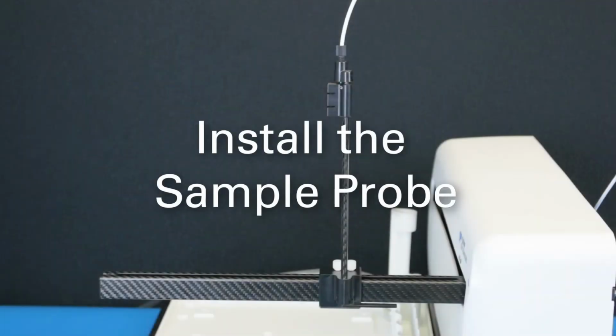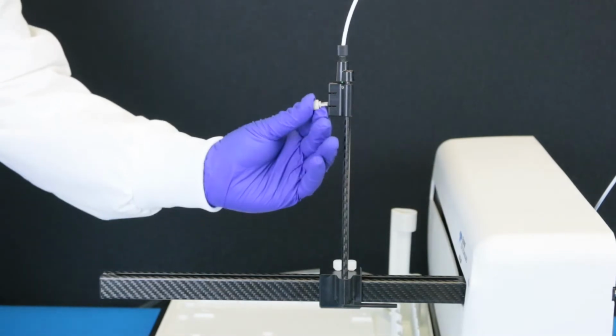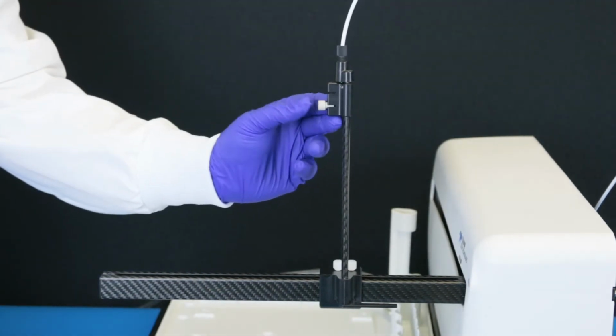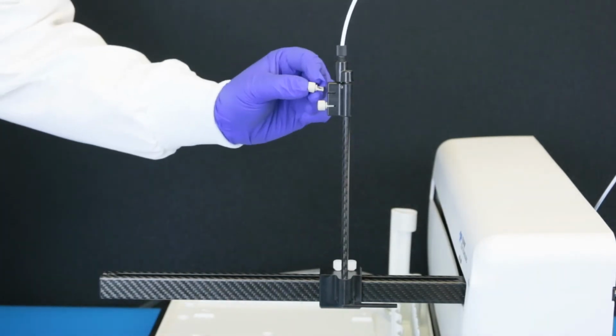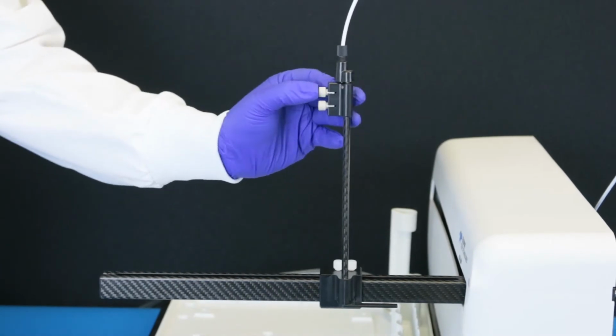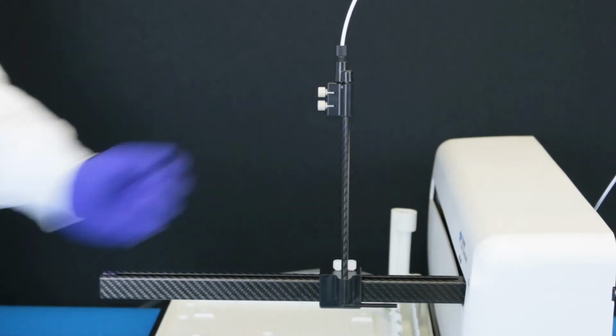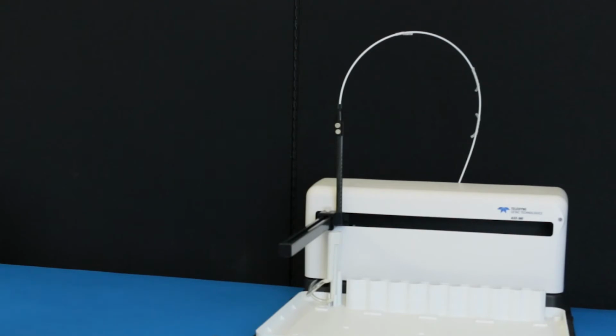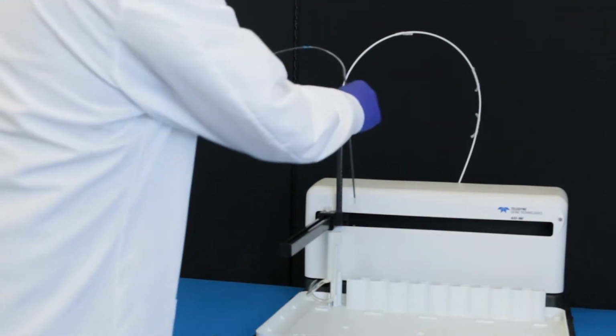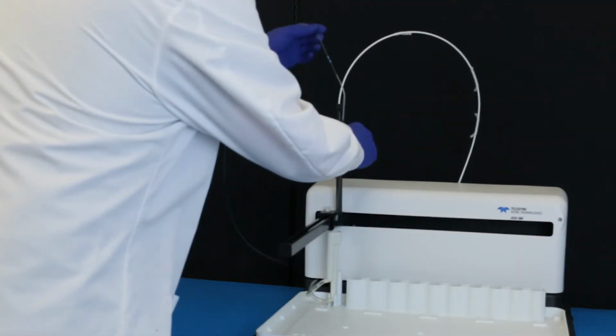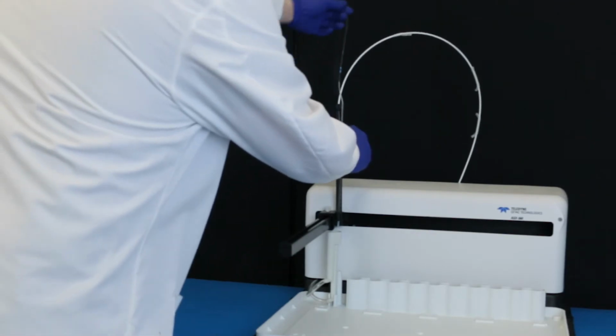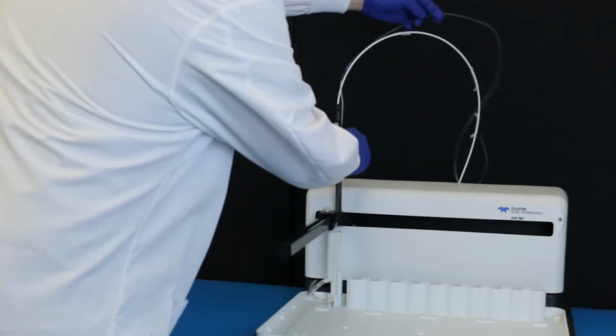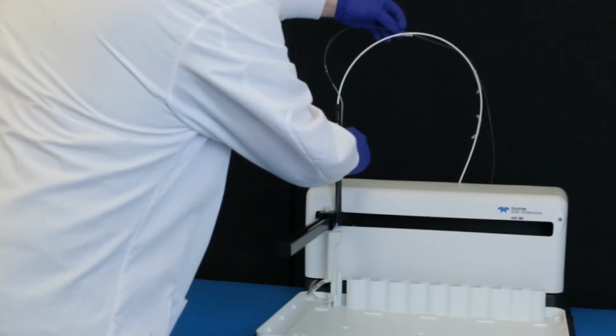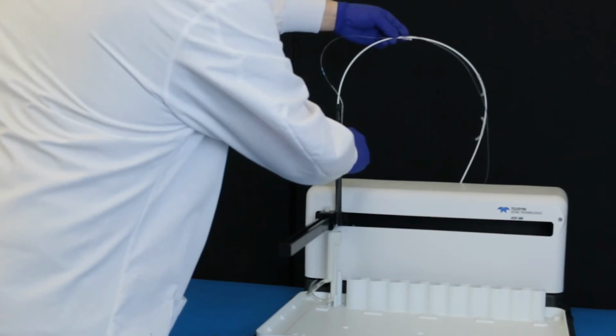To install the sample probe, insert the probe clamps into the Z-axis slider. You may need to loosen the nuts on the clamps before installing the probe. The sample probe must be trimmed to an appropriate length. To determine where to cut the tube, hold the tip of the probe even with the bottom of the Z drive. Now hold the sample tube alongside the spiral wrap. There should be a generous loop to allow movement as shown.